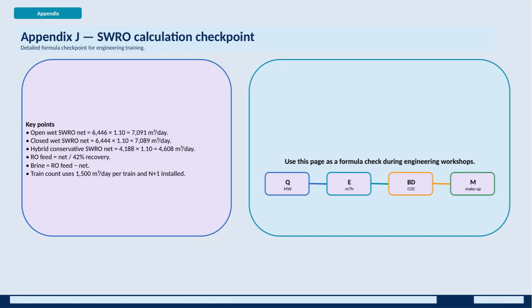This appendix serves as a detailed formula checkpoint designed to support engineering training, specifically focusing on the seawater reverse osmosis, or SWRO, process for the Batum Coastal Data Center water supply system. The training package covers several critical elements, including SWRO desalination, direct liquid cooling, and integration with cooling towers. Here are the key points to keep in mind. First, the open wet SWRO net water flow is calculated as 6,446 cubic meters per day, multiplied by a factor of 1.10, which results in 7,091 cubic meters per day.